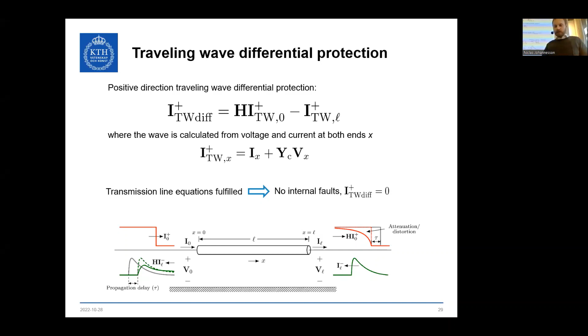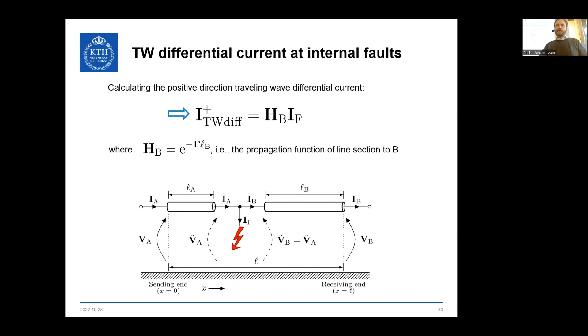So we know that it's stable during external faults. Then the question would be, what can we expect during an internal fault? Which you can calculate by considering your transmission line of length L as 2 pieces, basically. Each one fulfills the transmission line equations. Doing that, you will see that during this case, the differential current would be this HB times the fault current. So this is the propagation function of the line section between the fault and the receiving end, meaning that if the fault would be exactly at the remote or the receiving end, then this HB would be the identity matrix, and then you would actually see exactly the fault current.